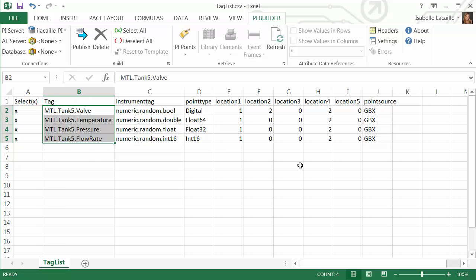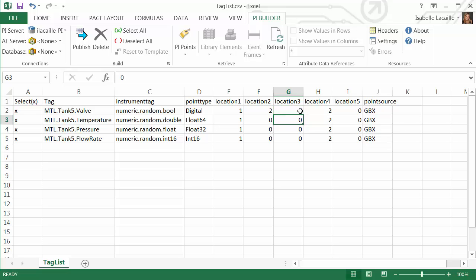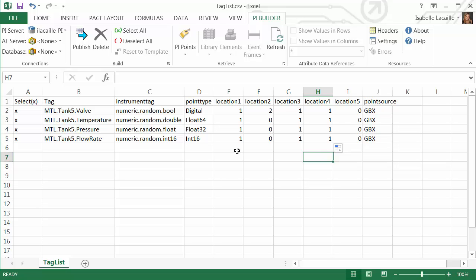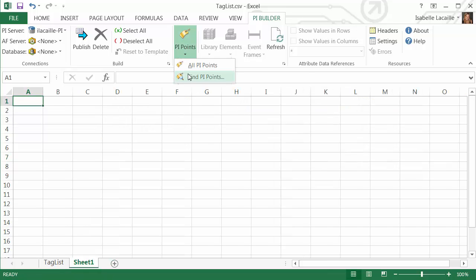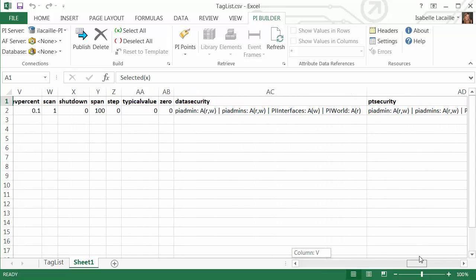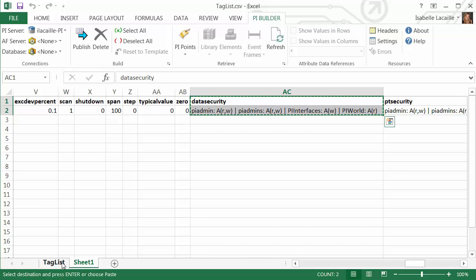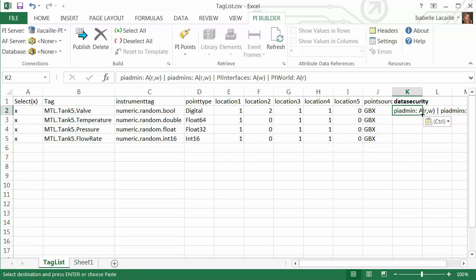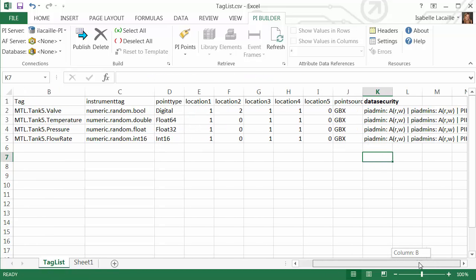I'm going to modify the tag names since they don't represent what I want to collect. Next, I also need to change Location 3 and Location 4. Location 3 is for the type of input point and Location 4 is the scan class — I want these points in scan class 1, so I'll change everything in that column to 1 and the scan class column to 1 as well. For parameters not listed here, the default will be selected. We actually had to change the default data security on the tag we created in SMT, so I'll import that tag in a separate sheet and copy the data security value across to every item in my list.